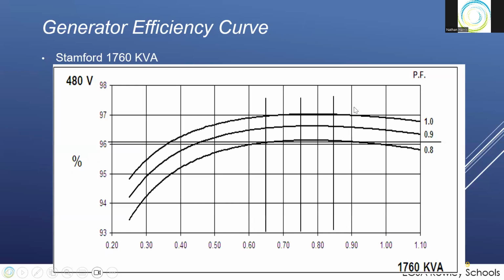Here's the generator efficiency curve for a Stamford 1760 kVA. Actually, you can see it here too. Here's a power factor of 1, which you don't often run at, but at a power factor of 1, your efficiency peaks out somewhere around this 75 to 80%. It's a much flatter curve, but it still peaks out in that same range, right?